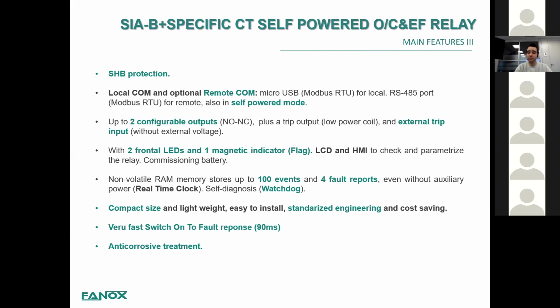And they are going to be kept in memory because they are stored in non-volatile RAM. Again, the time and date are fixed with the real-time clock. Also, we can have a self-diagnosis output configured, or watchdog. That is a very important requirement for most of our clients. This specific relay has a very compact size and is easy to install. And as I told you before, the combination of this relay and the CTs can give you standardized engineering and cost-saving benefits.